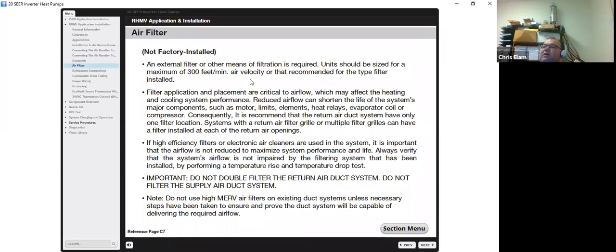The air filters are not factory installed. The external filter is required. Units should be sized for a maximum of 300 feet per minute air velocity, so that would be recommended for that type of filter. Ideally, you would want a 4-inch or even a 5-inch media filter to reduce static pressure. Filter application and placement are critical to airflow, which may affect the heating and cooling system performance. It will also increase the static pressure.